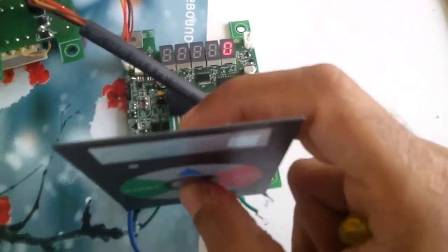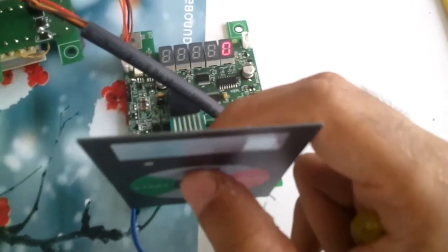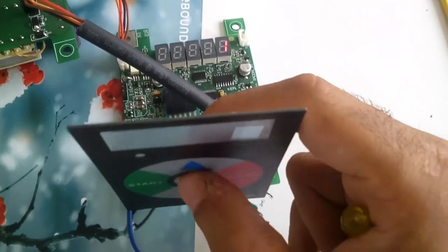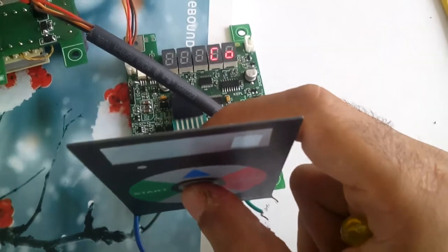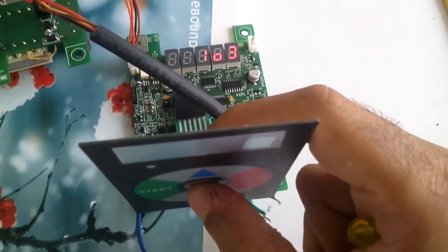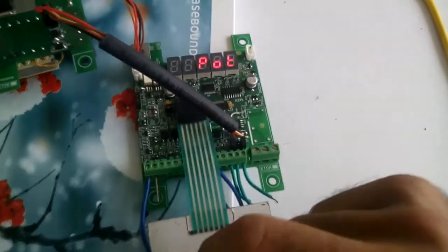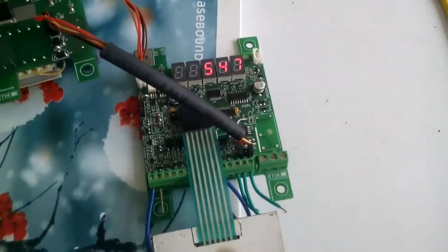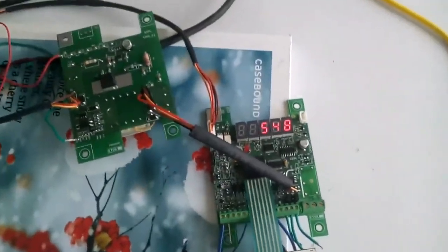Now we will go to the self-test mode. When we enter this parameter as 1, the self-test starts. Let's see that. Current offset test, it's clear now. Then IO test 1, 2, 3, 4, it's clear now. Then comes a pot test, it is also clear. Now there is the under voltage test, the under voltage trip test basically.